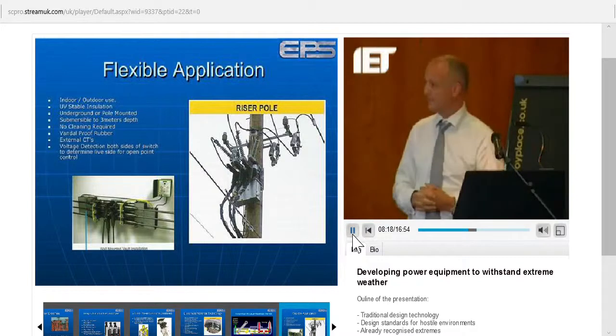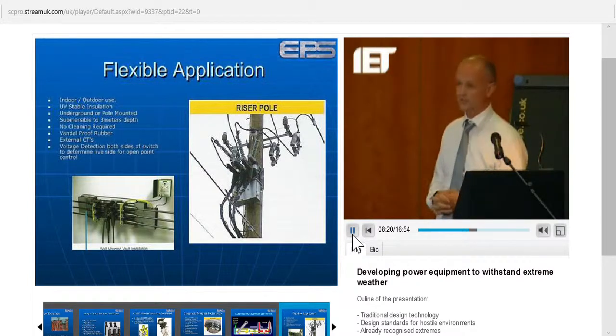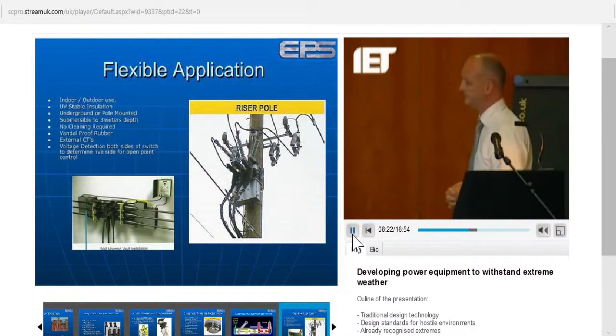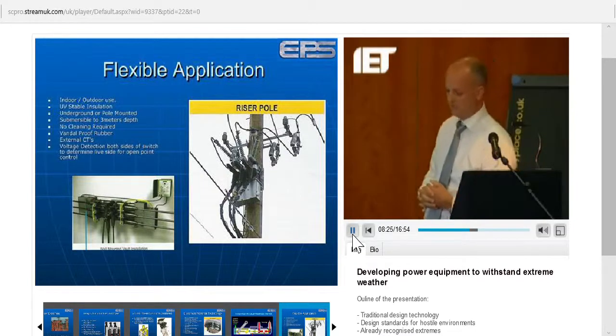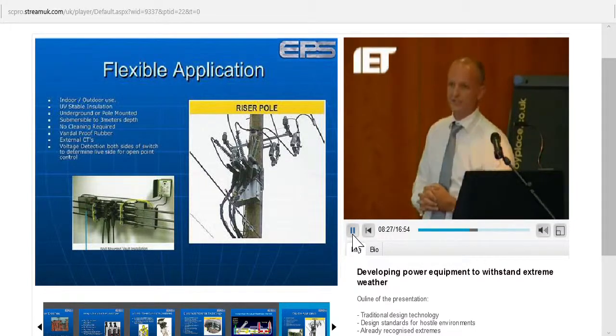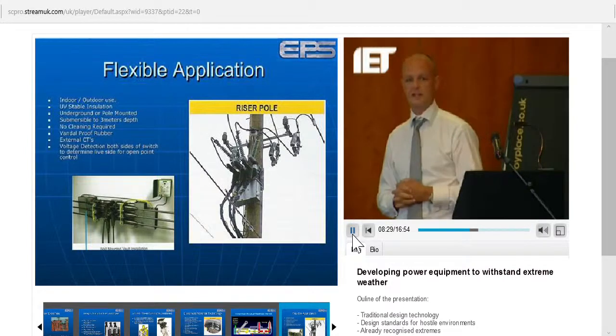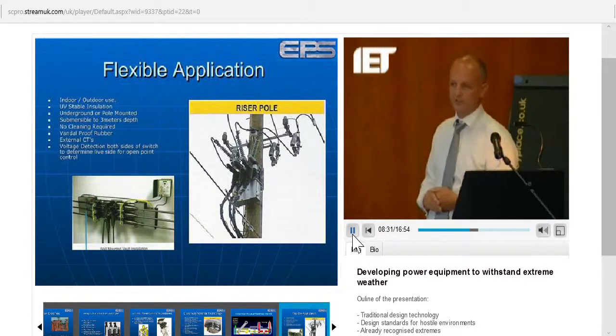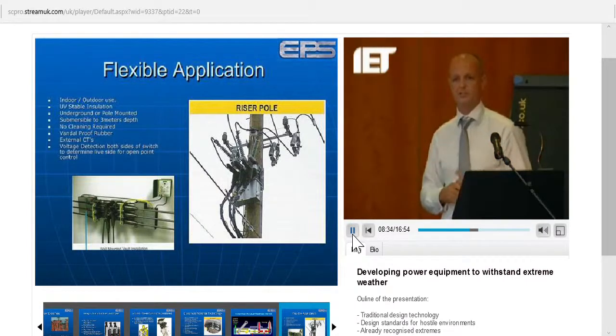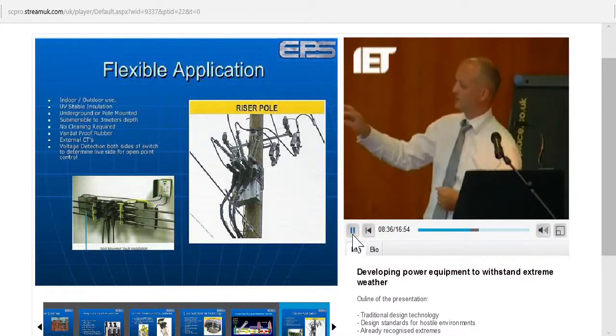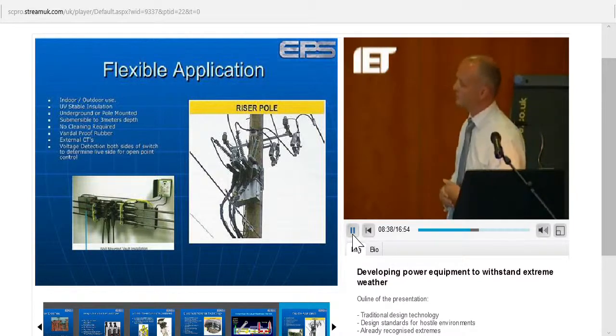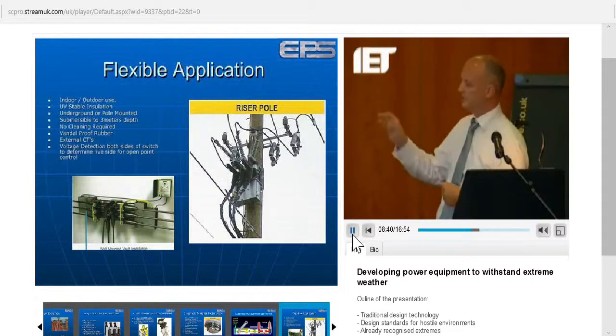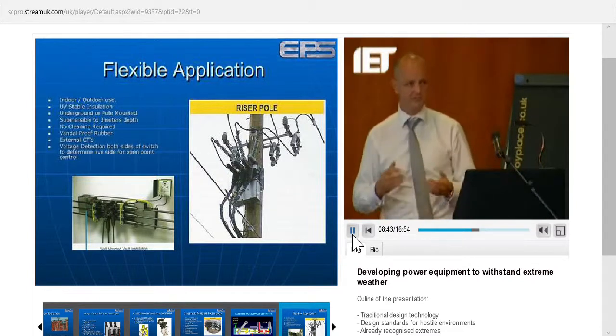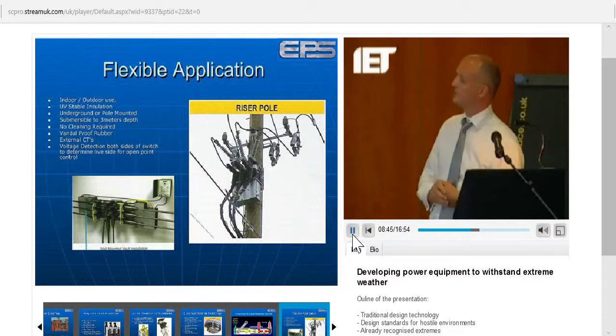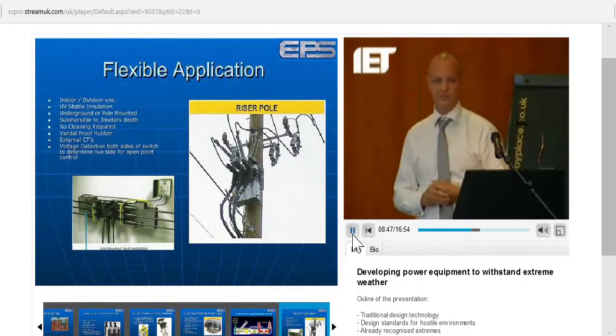There are a number of accessories as well that come with this, enabling us to automate this. We have voltage detection. You can see on the bottom picture on the left there's some yellow cables, so we can detect which side of that switch has got voltage on it. So if we want to do simple loop automation schemes, we can couple this up to the controller system. We also have current measuring CT blocks which can be added. These can be retrofitted after installation as well, because the cables are simply unpluggable and pluggable back on again.